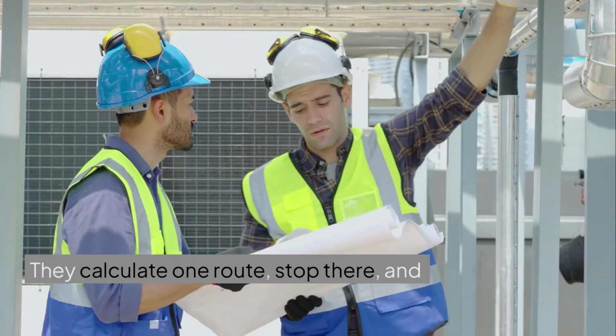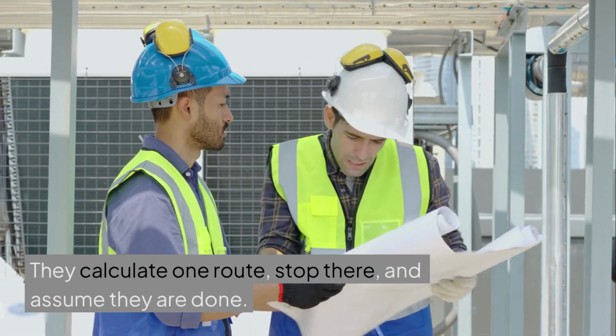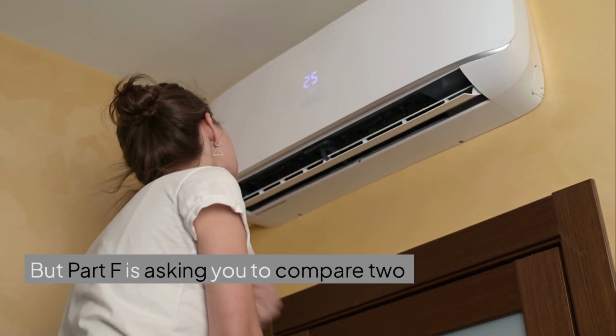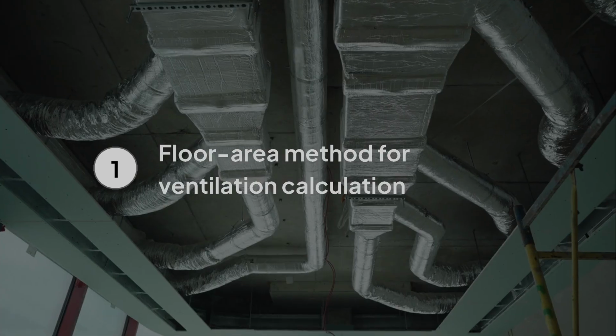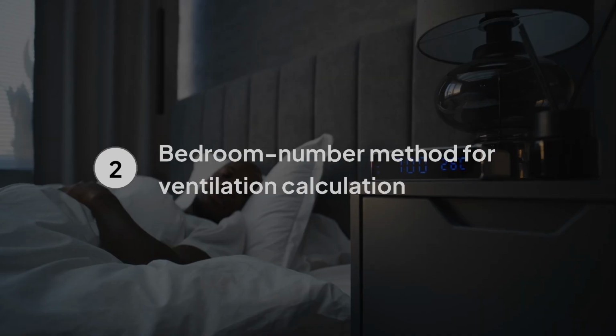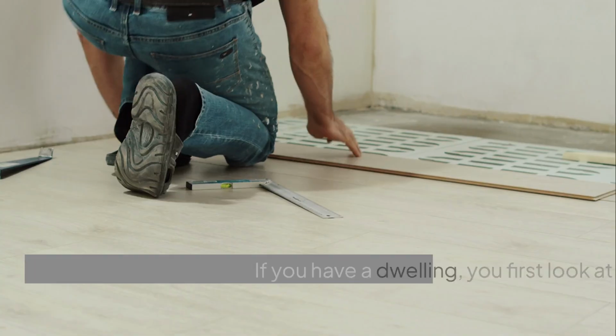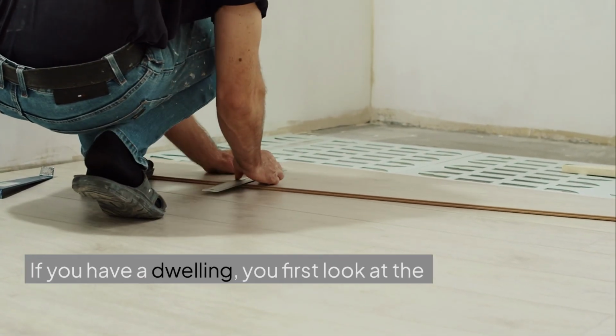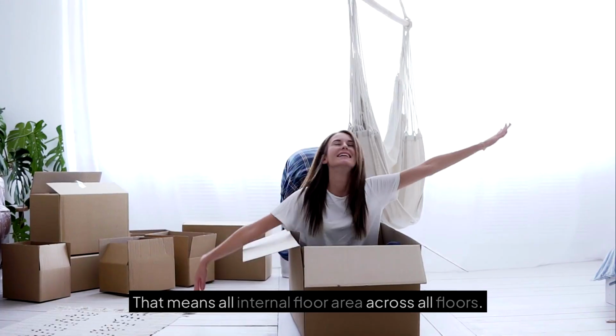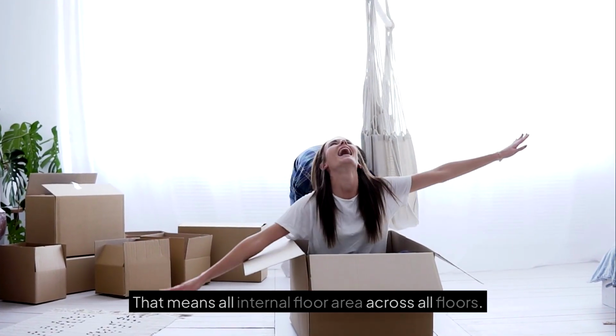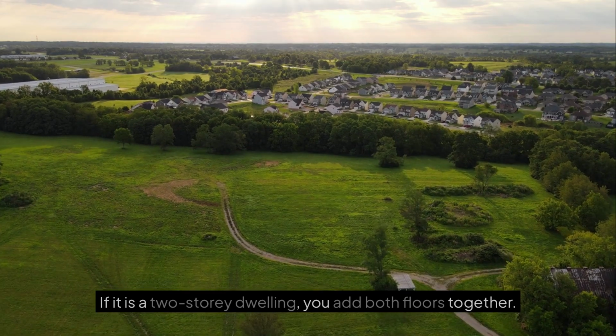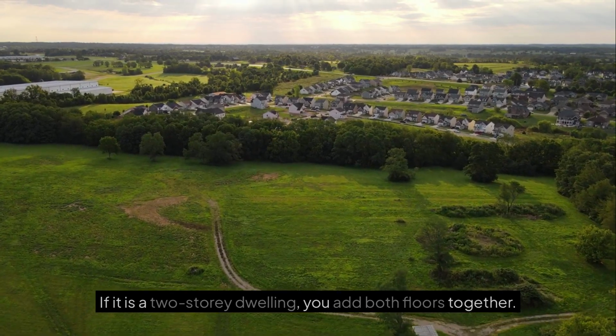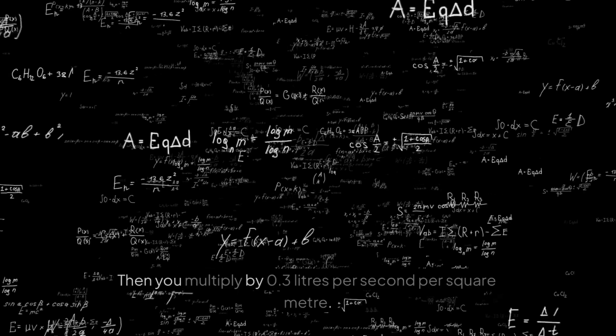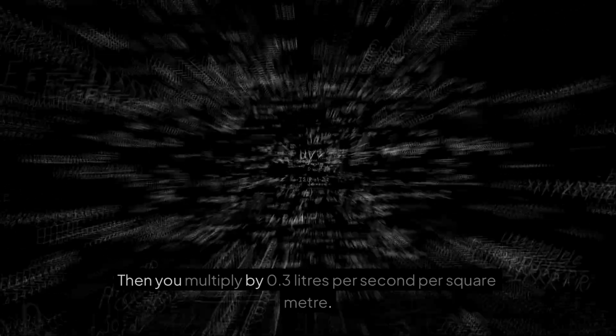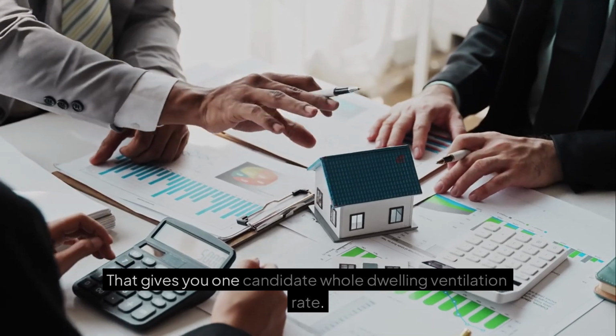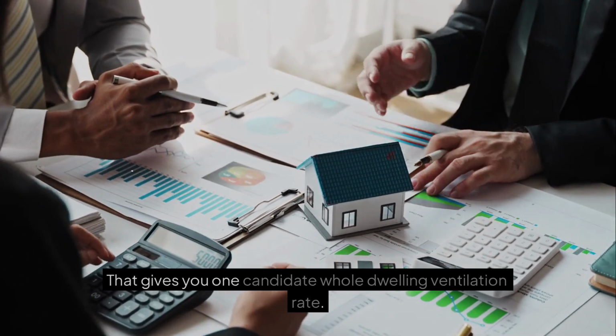They calculate one route, stop there, and assume they are done. But Part F is asking you to compare two methods. Floor area method, bedroom number method. So let's simplify that. If you have a dwelling, you first look at the internal floor area. That means all internal floor area across all floors. If it is a two-storey dwelling, you add both floors together. Then you multiply by 0.3 litres per second per square metre.